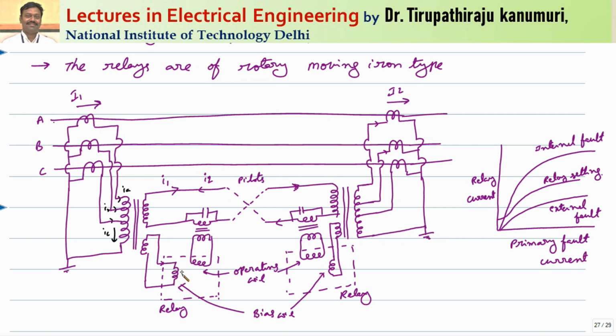That means the more the value of the current, the more will be the biasing effect. The advantage of this biasing coil is that for through faults, even though there is a mismatch in the CT characteristics of these two CTs, the opposing or restraining torque is proportional to the current. For through faults the current is more, so automatically the restraint force is more. This will compensate for any unbalance. Now the current passing through your operating coil will be equal to I1 minus I2, and according to I1 minus I2, the secondary side current will be induced in these coils.